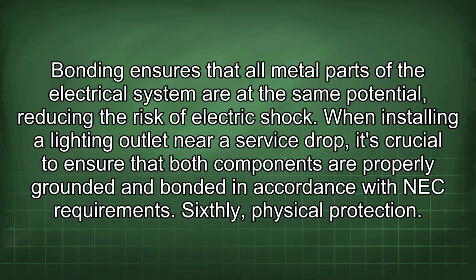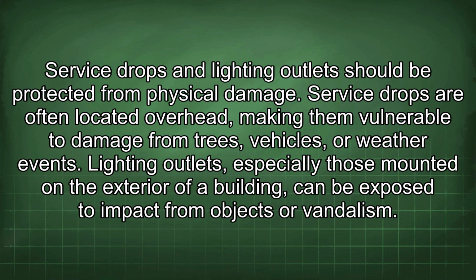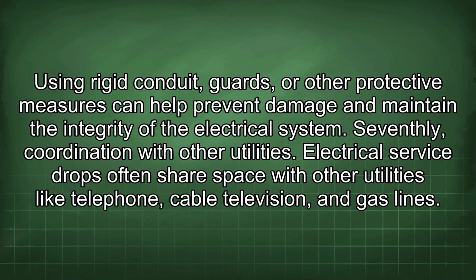Sixthly, physical protection. Service drops and lighting outlets should be protected from physical damage. Service drops are often located overhead, making them vulnerable to damage from trees, vehicles, or weather events. Lighting outlets, especially those mounted on the exterior of a building, can be exposed to impact from objects or vandalism. Using rigid conduit, guards, or other protective measures can help prevent damage and maintain the integrity of the electrical system.